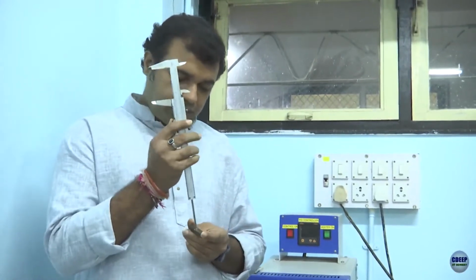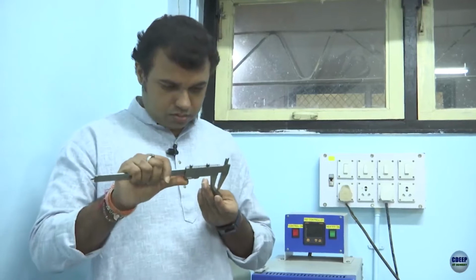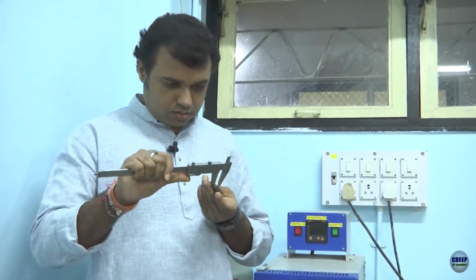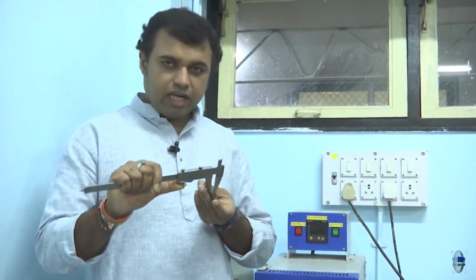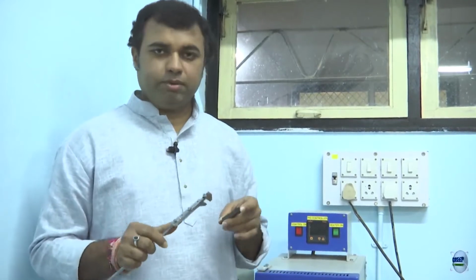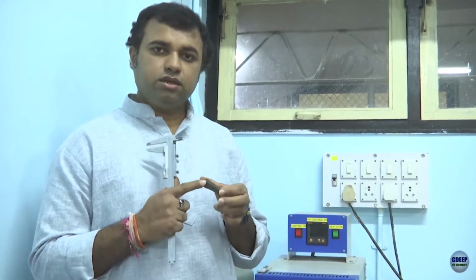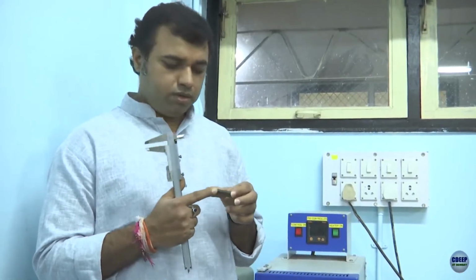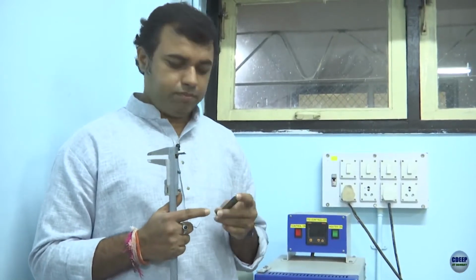We call this a notch specimen. It is notched at the center. The depth of the notch is 2 mm, with the specimen itself 8 mm at that point. So the dimensions are 10 by 10 cross section, and the length is 55 mm. The notch depth is 2 mm.